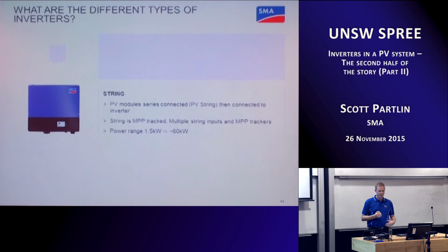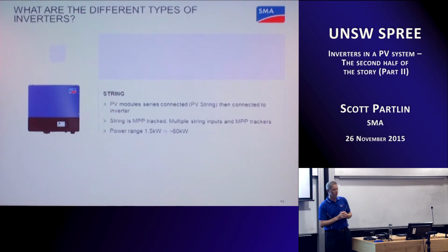install larger systems, that's where the next common inverter technology comes along, and that's a string inverter. So a string inverter, rather than being individually connected to each PV module like a microinverter, as the name suggests, takes strings of PV modules as its input. They take much higher voltages. They can be either single phase or three phase, and they will typically have power ranges, this is just a typical range, they may go a little bit higher, I didn't have a look at everything out there on the market, but typically in a range of 1.5 kilowatts to 60 kilowatts. And these can be used either as one unit on one site or many units on one site to achieve the power needs of that site.